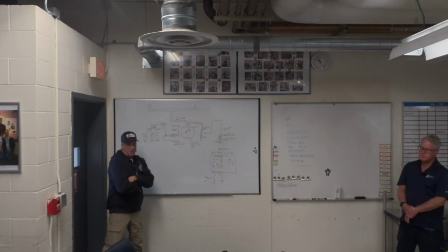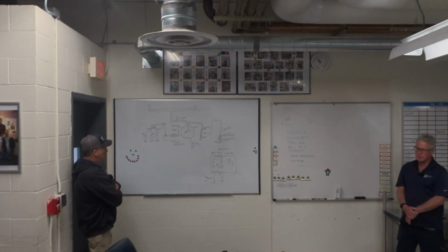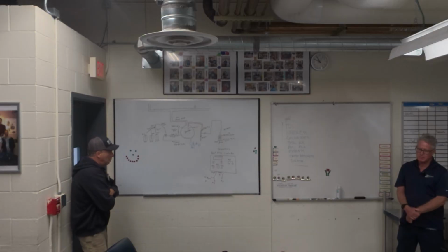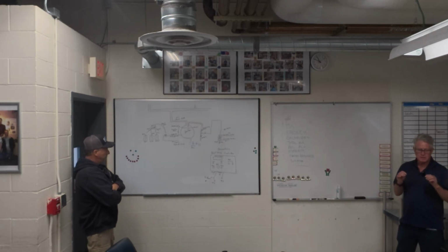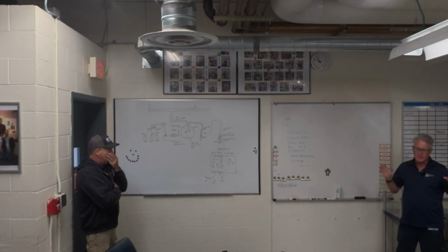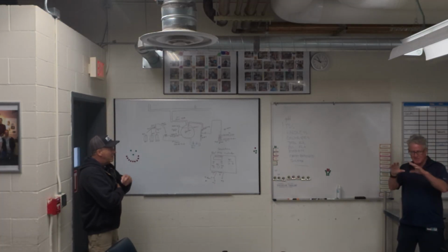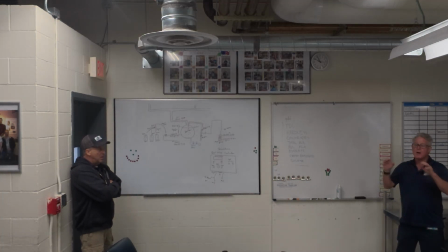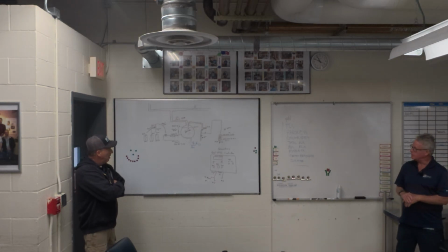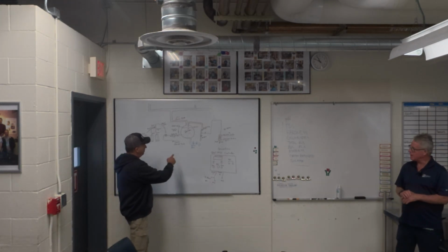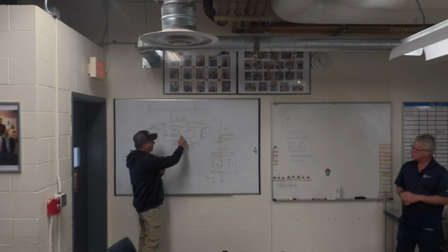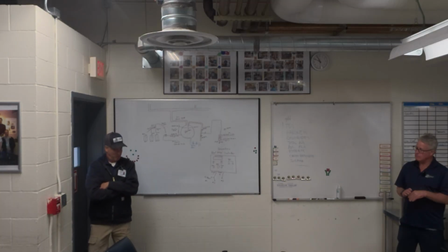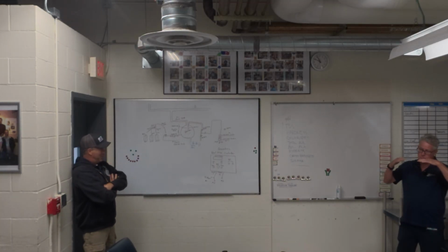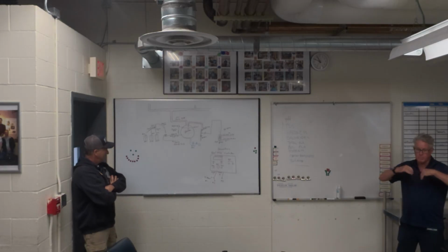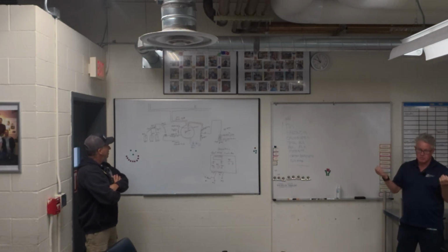As a unique part of Chemtech, we use a product in our boiler compound called lignosulfonate, which is lignin pitch from trees. It's an all-natural product, kind of a gooey substance, and it gets in there and helps drop everything to the bottom. We're sharing a little bit out of that proprietary knowledge here. If they don't bottom blow, this stuff just packs up and gets really ugly, and you could warp the tubes in the boiler, overheat them, and then they start to separate.